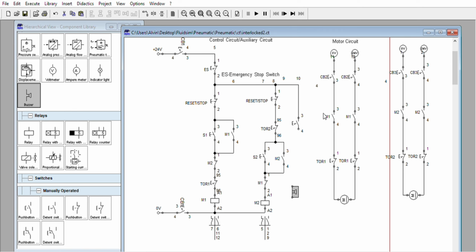If you need the lamp, you can have the lamp. You can parallel the lamp, but be sure the lamp has a transformer. The lamp, that pilot lamp with transformer inside. You cannot parallel an inductive and resistive load directly.